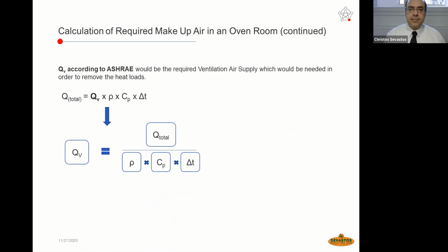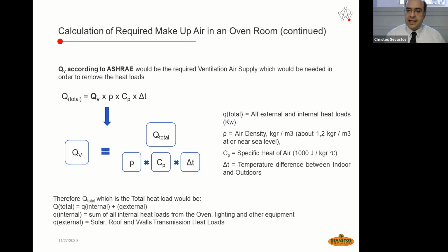Calculation of required makeup air in an oven room. The air ventilation rates, according to ASHRAE, would be the required ventilation air supply which would be needed in order to remove the heat loads. In order for us to be able to calculate the air ventilation rates in a tunnel oven, we need to have this equation. This equation is based on the division of the overall external and internal heat loads by multiplying the air density, the specific heat of air, and the gradient of T, the temperature difference between indoor and outdoor. So the first step in order for us to calculate the air ventilation rates would be to calculate the overall heat.